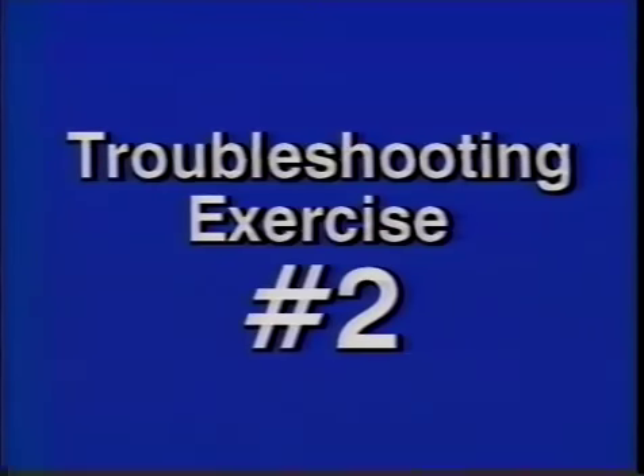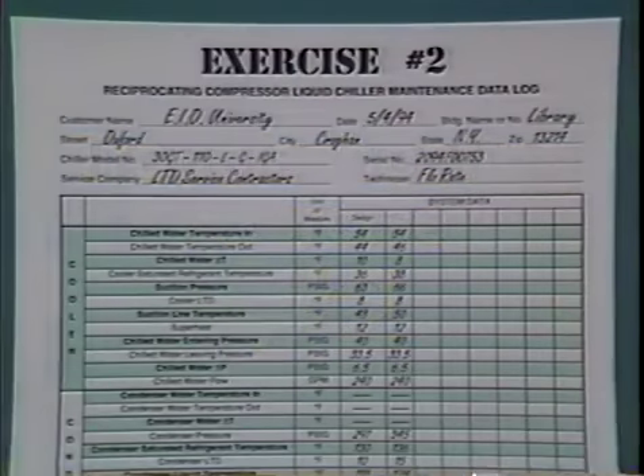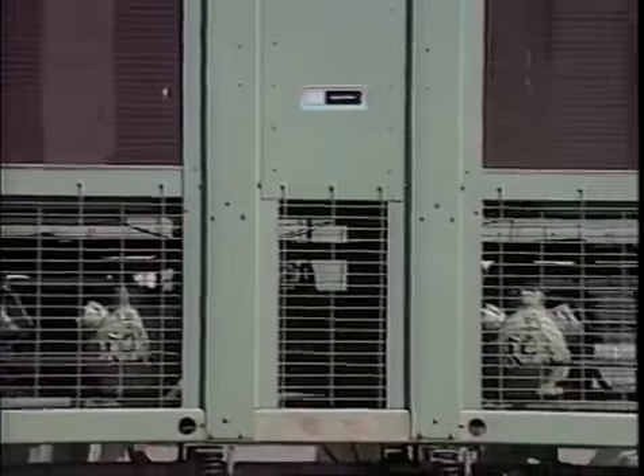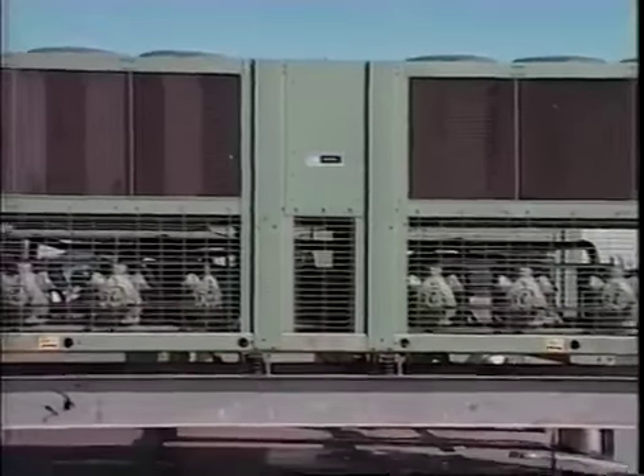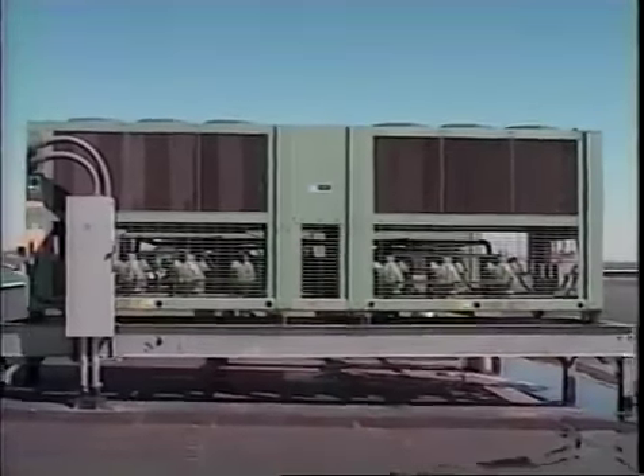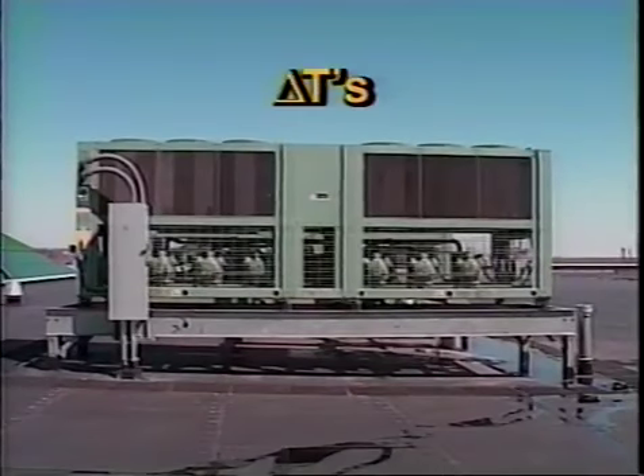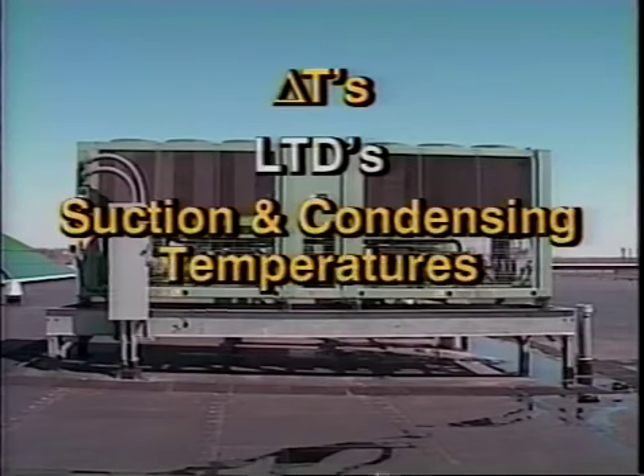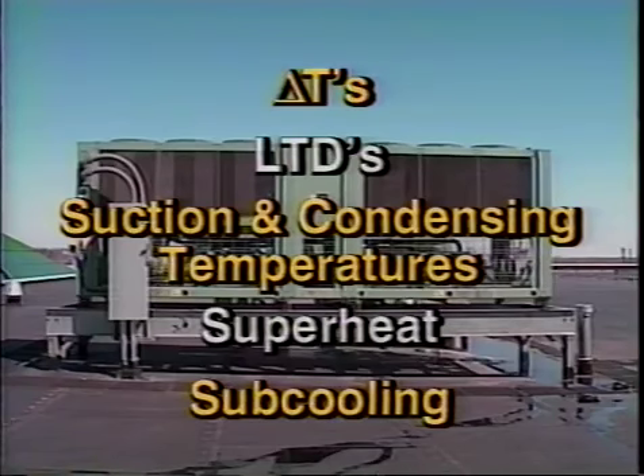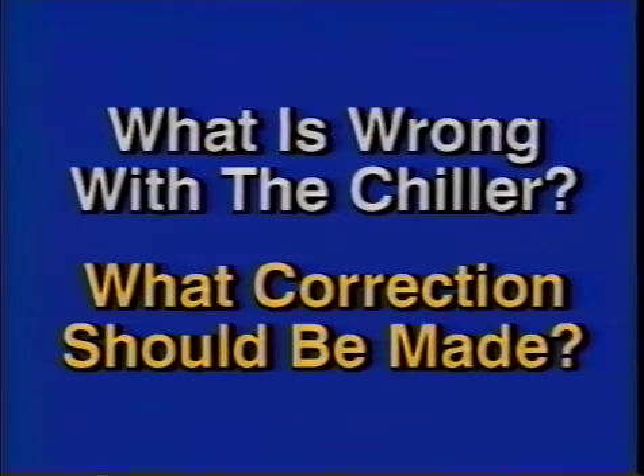Let's look at exercise 2 in your workbook. All the information you need to solve this problem is listed on the log sheet identified as exercise number 2. This is a chiller with an air-cooled condenser on air conditioning duty that's not making capacity. Use the same procedure as in our first exercise. Compare the delta T's and the LTDs, saturated temperatures, superheat, and subcooling to the design data. We want you to answer what is wrong with the chiller and what correction should be made. Now stop the tape and go to your workbook and do exercise number 2. When you have completed the exercise, restart the tape for a review.